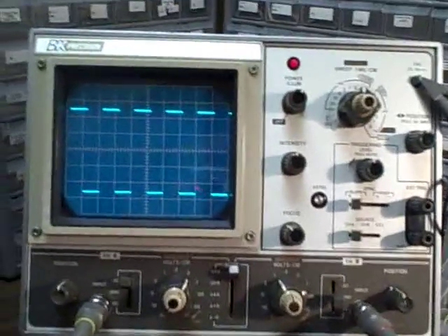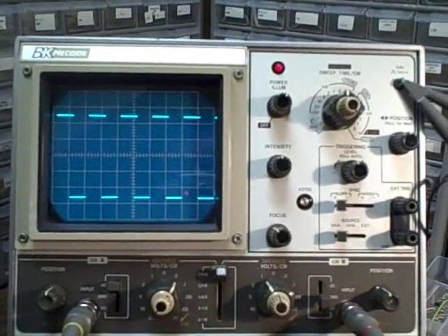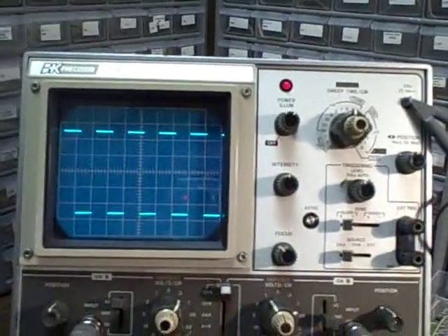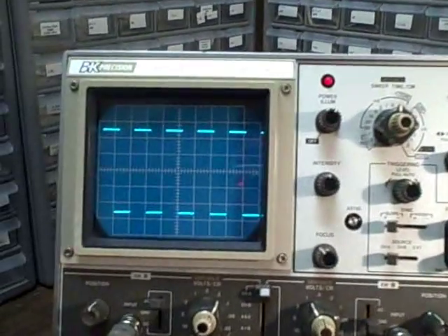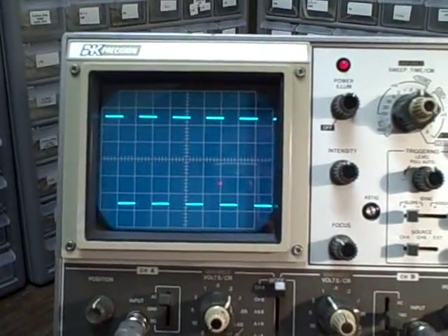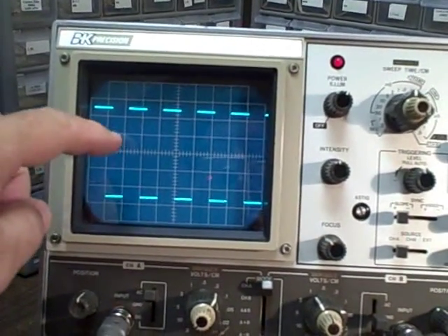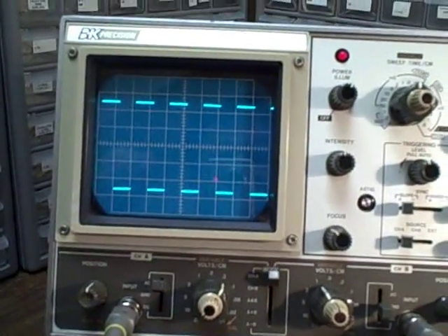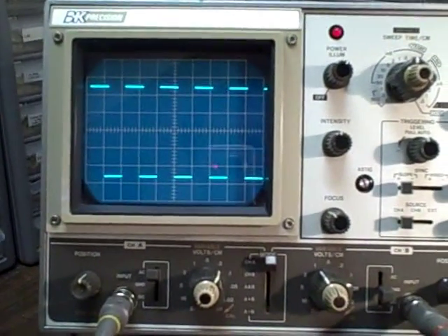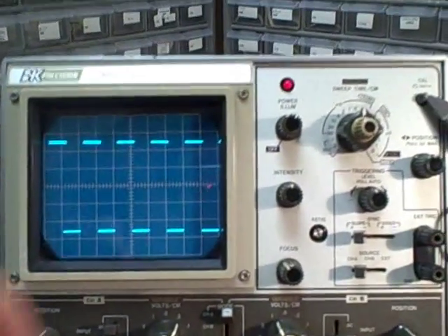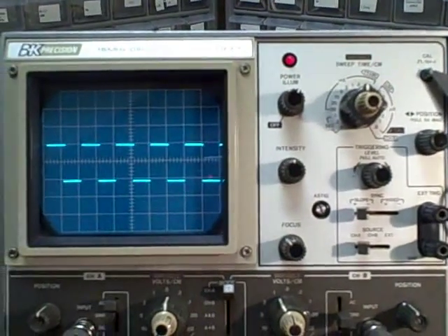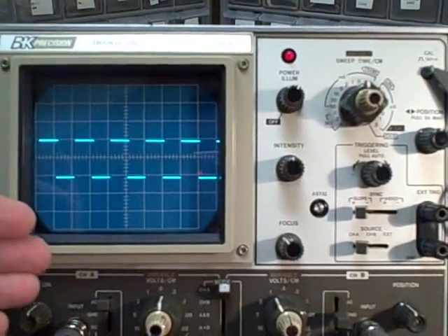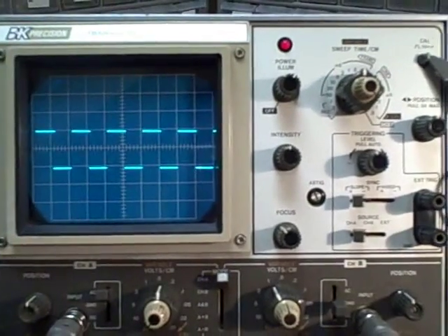Okay, we have both probes connected to the calibration point on the oscilloscope. We get 1 volt peak-to-peak provided to the input channels. Right now we're looking at channel A, and we're at 0.2 volts per division. So 0.2, 0.4, and then a half would be 0.5 volts positive, 0.5 volts negative, 1 volt peak to peak. And if we change to 0.5 volts per division, we're up 1 division, down 1 division, 0.5 up, 0.5 down, 1 volt peak to peak.